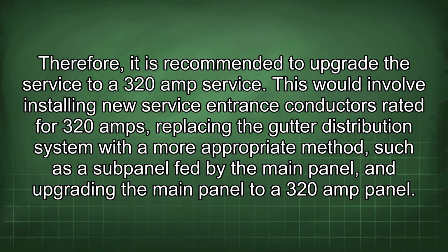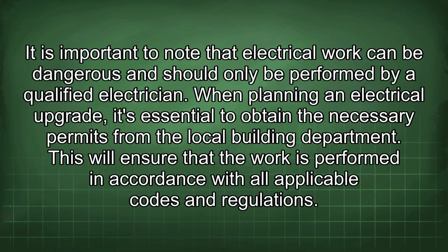This would involve installing new service entrance conductors rated for 320 amps, replacing the gutter distribution system with a more appropriate method, such as a sub-panel fed by the main panel, and upgrading the main panel to a 320 amp panel.